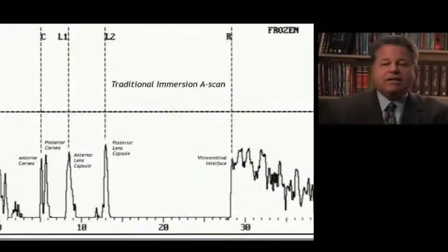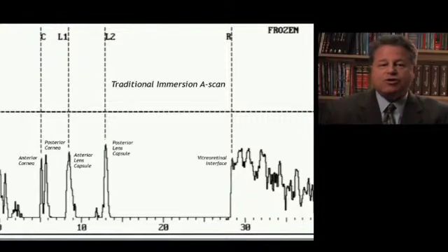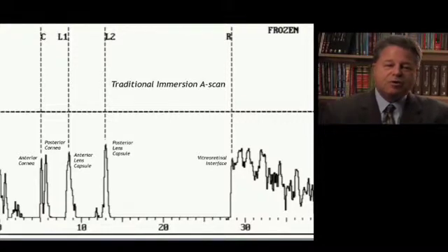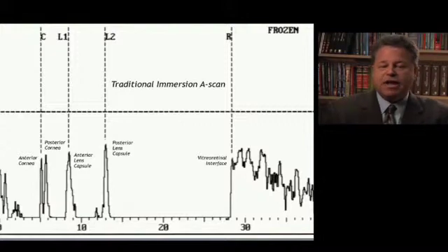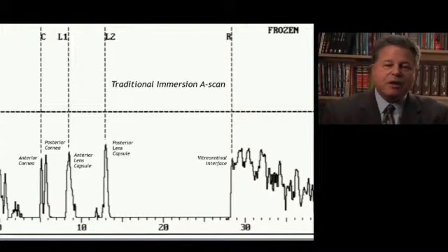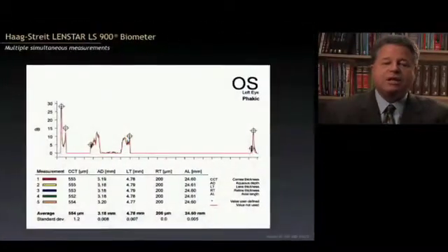Getting into how the measurements are actually done — this is what a traditional immersion A-scan looks like. We see spikes for the anterior cornea, posterior cornea, anterior lens capsule, posterior lens capsule, and the vitreoretinal interface. What Haag-Streit has done is copied this as a presentation of the axial length measurement so that you can go in and adjust the measurement gates in pretty much the same way as you would with an immersion A-scan.